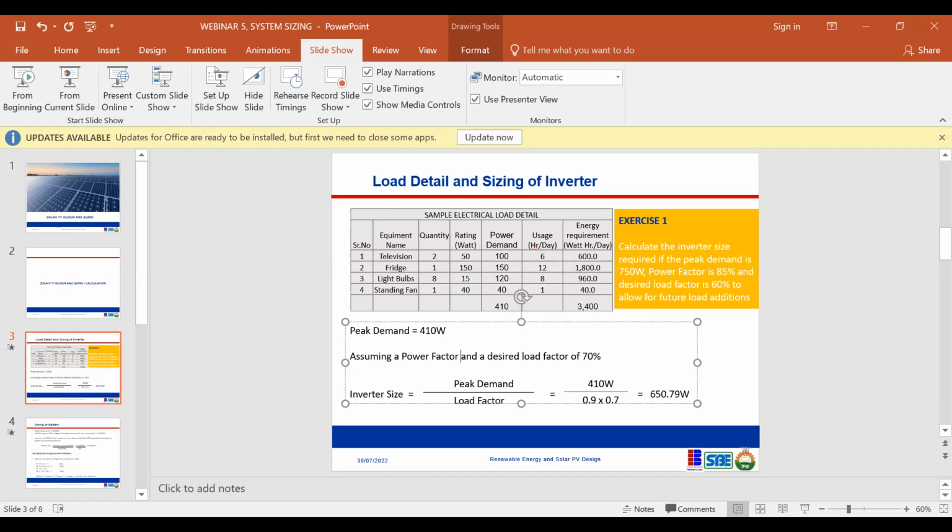Okay, Mr. Chiva, most of the housing power factors are very badly done. Sometimes they go lower than that. So are we supposed to determine the one from the building first before we can calculate? So like I said, for design purposes, please use 80. For design purposes, 75 is what I use. You can decide to use 75, but whatever you're using, state it. Yes, state it.